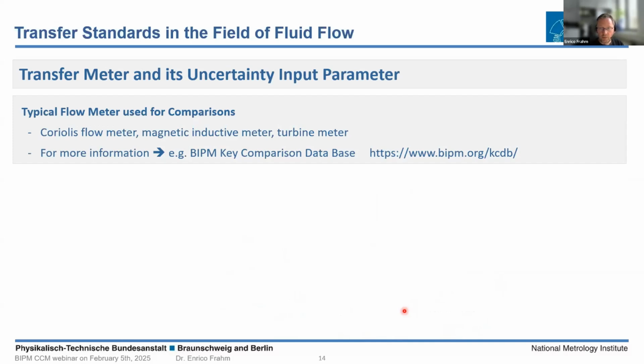So typical flow meters used for comparisons are Coriolis flow meters, magnetic inductive meters, and turbine meters. And each of these instruments is characterized by its own advantages and disadvantages. So if you want to get more information about use, transfer standards, evaluation procedure, and flow ranges and fluids and so on, you can have a look into the very well known BIPM key comparison database. There you will find any information about key comparison, supplementary comparisons, and use transfer standard and so on. So really interesting to have a look to this database.